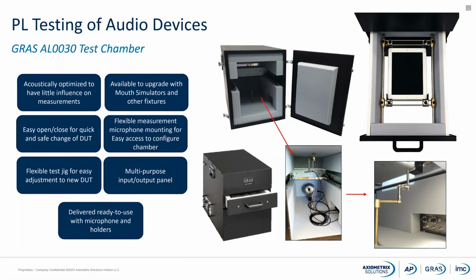So if we see this picture here, inside the AL30, we have different mounting points on the top of the box and different mounting points on the bottom. These mounting points can be used to set up measurement microphones or a sound source. And here we can see that we have a measurement microphone on the top, a measurement microphone on the bottom, and a mouth simulator that is being used as a reference sound source.